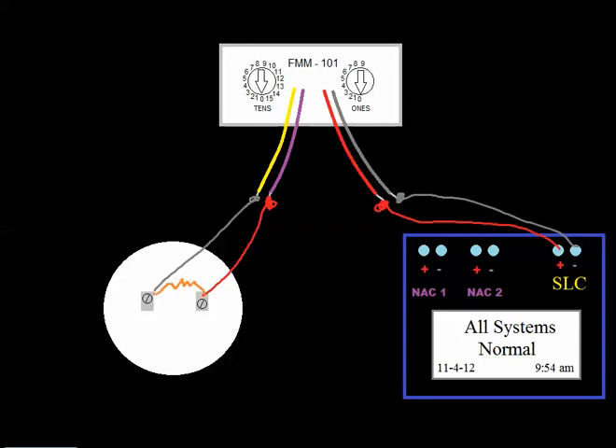And then I'd put my resistor across here. So a current's going to flow. I don't remember which one of these is positive or negative, but it doesn't matter because you're always just using a contact, a normally open device that doesn't draw any current. And so that's how you would monitor the heat detector.